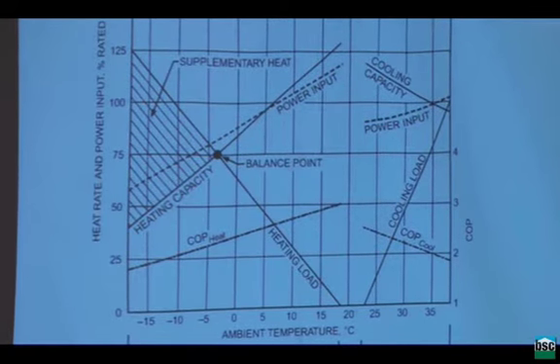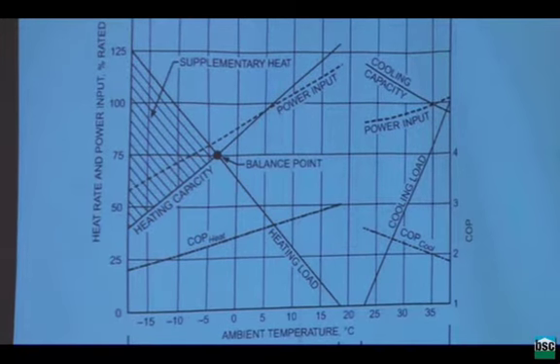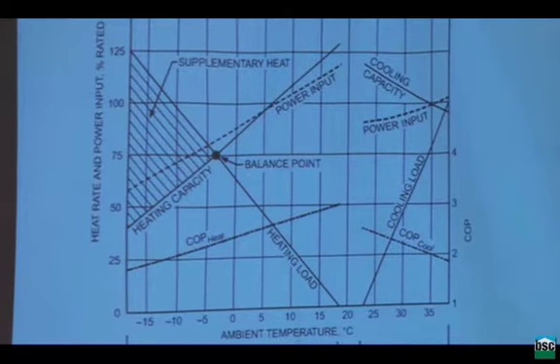Completely commonsensical, right? The reality of heat pump equipment is the heating capacity line that slopes upward on the left-hand side, labeled heating capacity. And when it is not very cold outside, it has lots of capacity because the temperature lift is small. As it gets colder and colder, the temperature lift gets larger, it has to pump harder, and so its capacity drops.